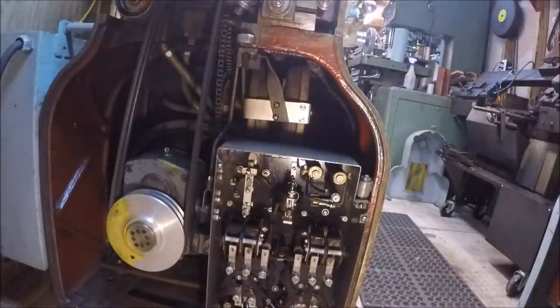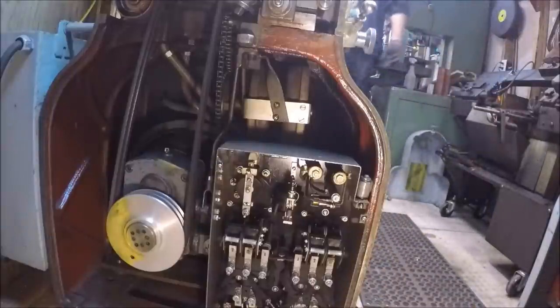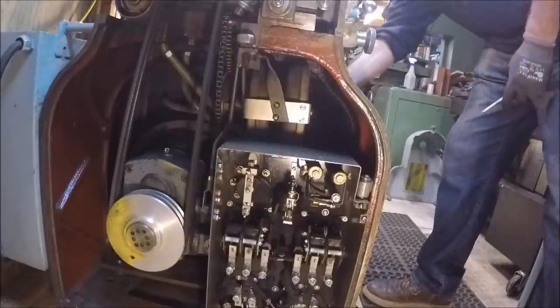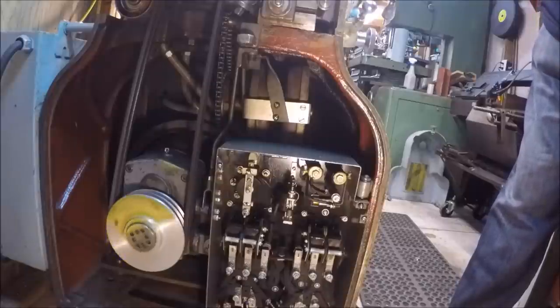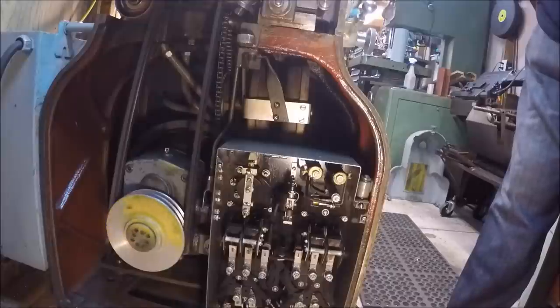This is the AP switch here, so let me fire it up. I've got the rheostat on the RPM set all the way to low and I'll engage the spindle. You can see the contactor is closed there. The machine's running and if I was to re-engage the spindle, it'll start back up again.